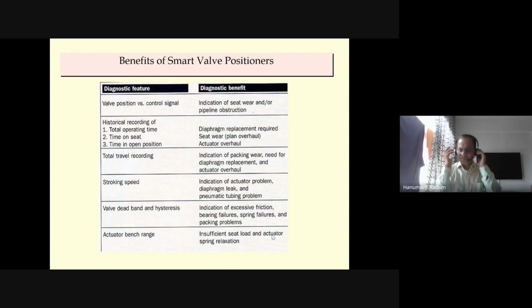So if you see here, diagnostic features and diagnostic benefits, there are various important features available. Valve position you can get in digital format. Historical readings you will get. Total travel recording you will get. Stroking speed you will get. Valve deadband and hysteresis also you will get. And actuator bench range. So these earlier were not available.